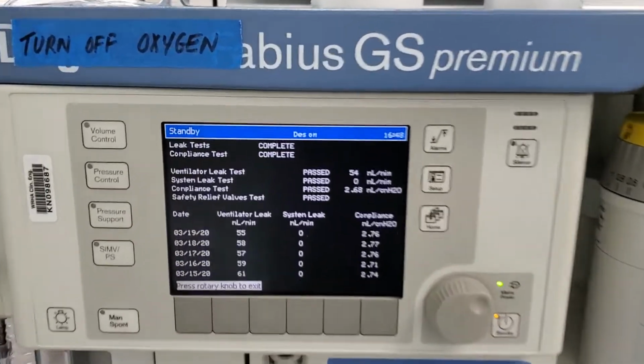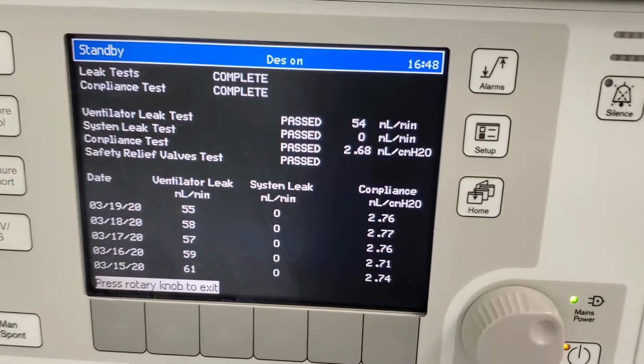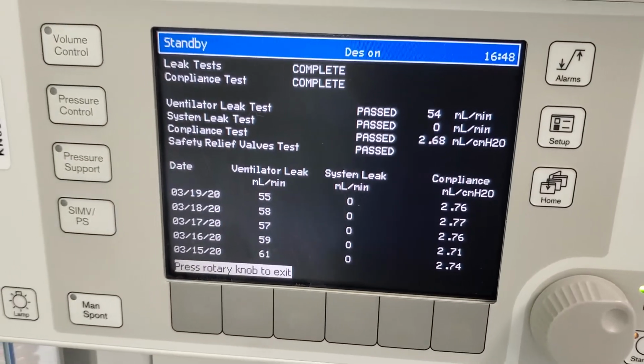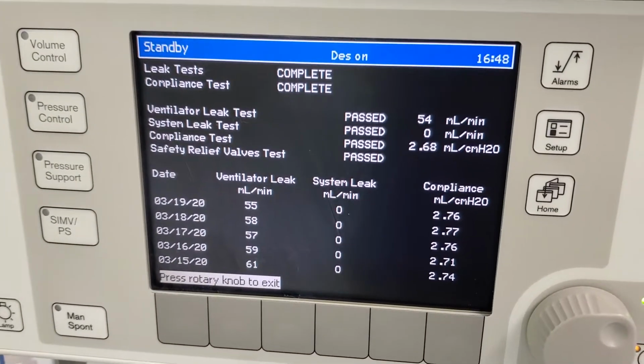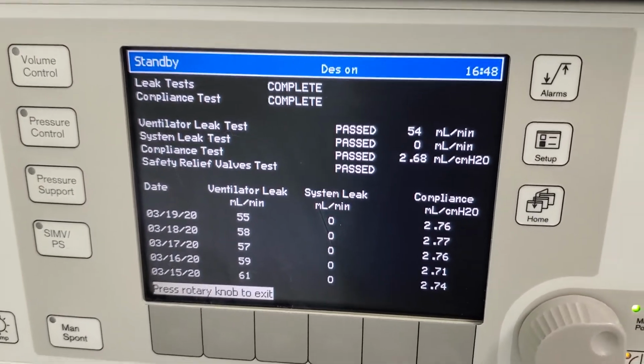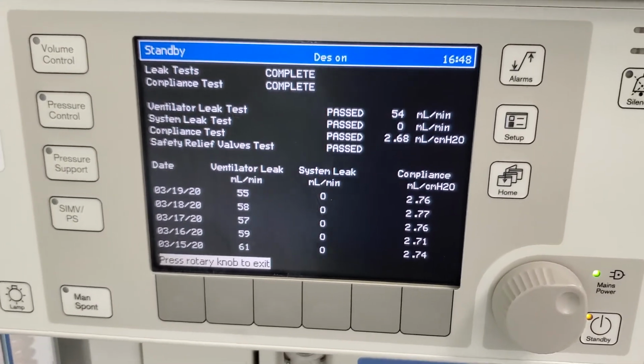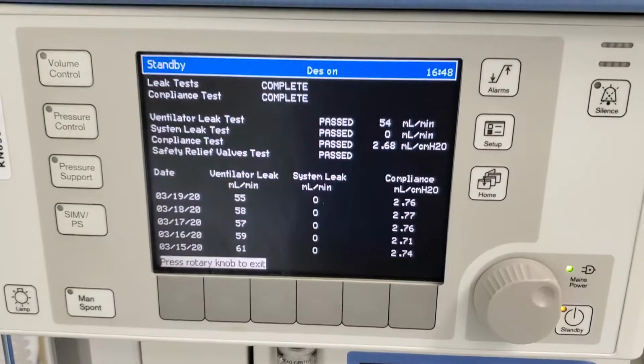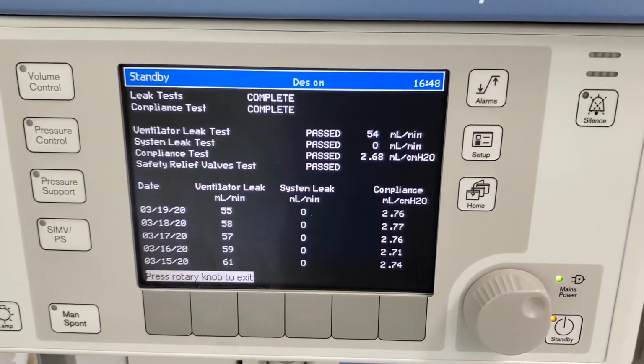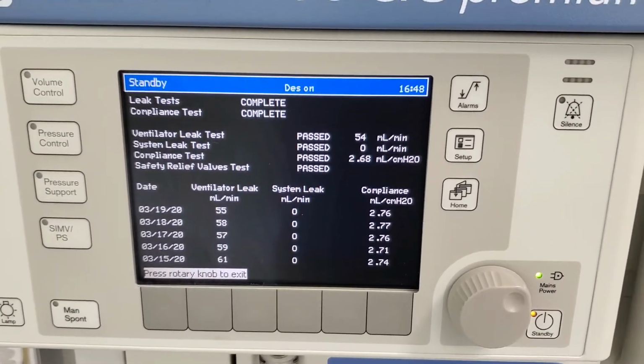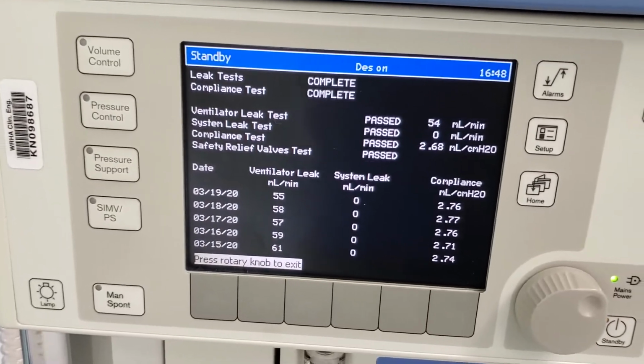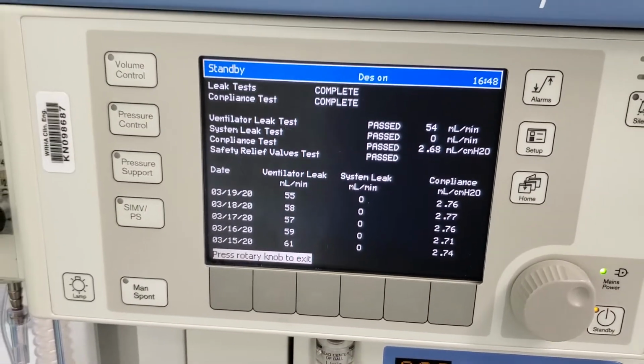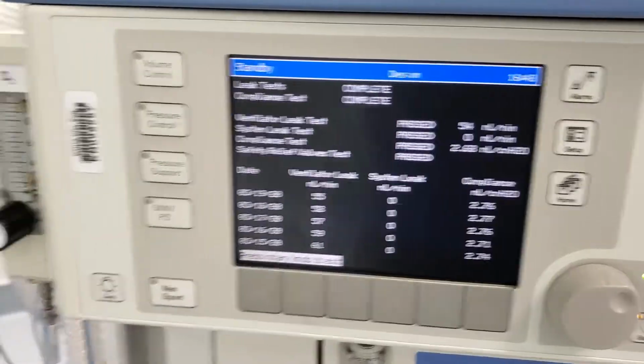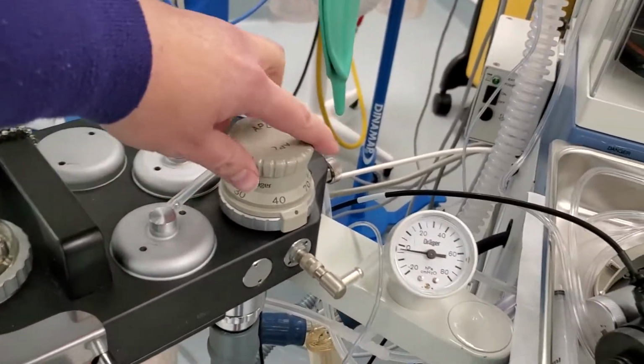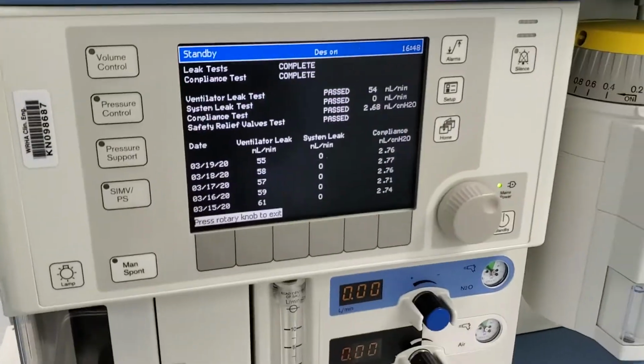So everything has passed. If there was a leak, I would tighten my connections, making sure that there were no gaps in the breathing system. There are other things that we can check, and if it does break up into ventilator leak versus system leak, again in the supplemental notes, the components that could be responsible for the leak are listed in there. At the end of the test, we just reopen the APL valve and the machine is ready to go.